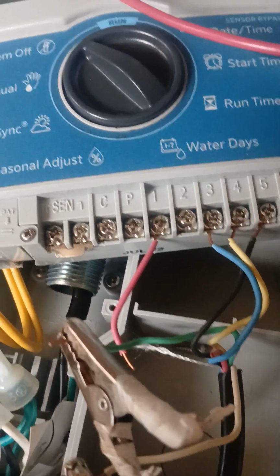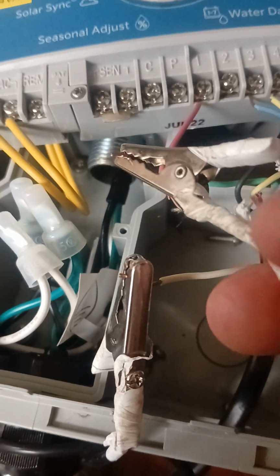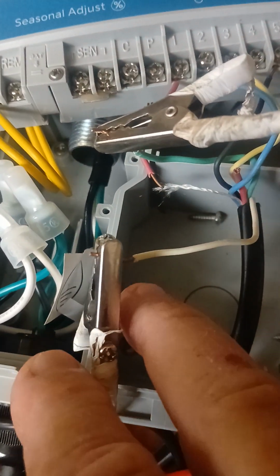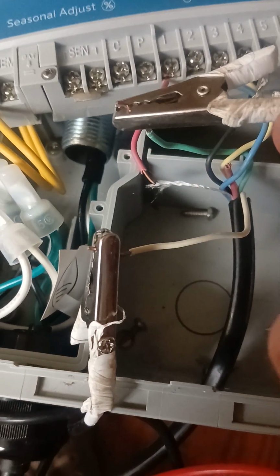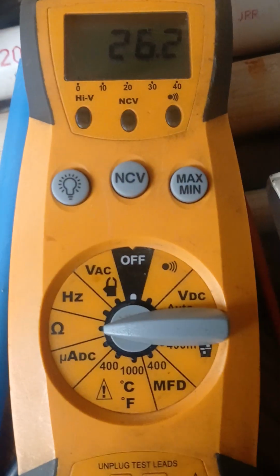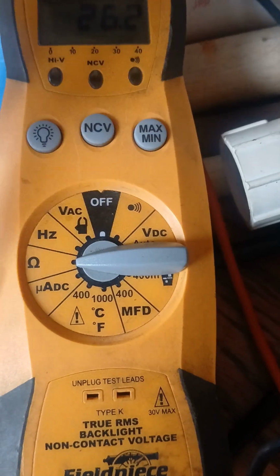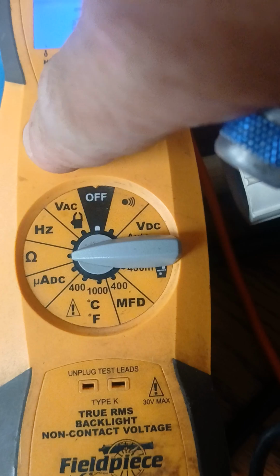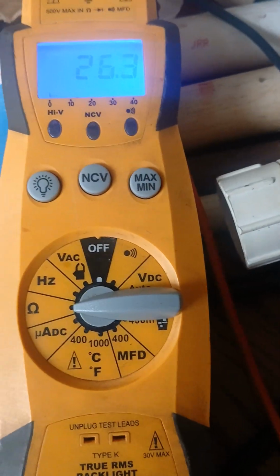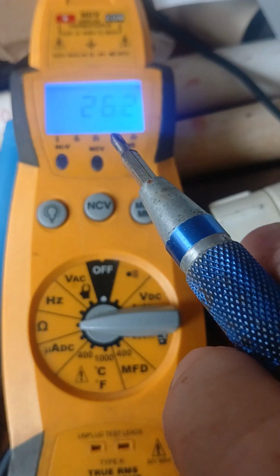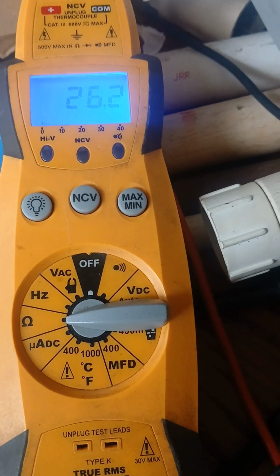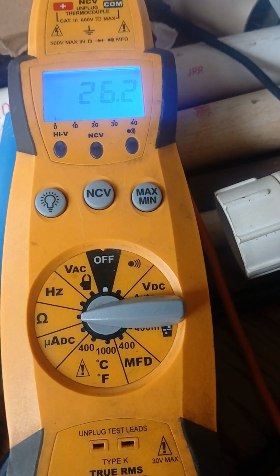So we've got it tied in here. What we did is took this wire off, and then I just used these alligator clips. It's not advisable to do this with high voltage, but this is low voltage. So I took one alligator clip and put it on the white, one alligator clip and put it on the green. We have the multimeter set to the ohms position. We'll put the backlight on and see what ohms we're reading. What we're reading here is 26.2 ohms. So in the range of 20 to perhaps 60, it's not an exact science, but plus or minus, the valve may test good. This is a new valve.